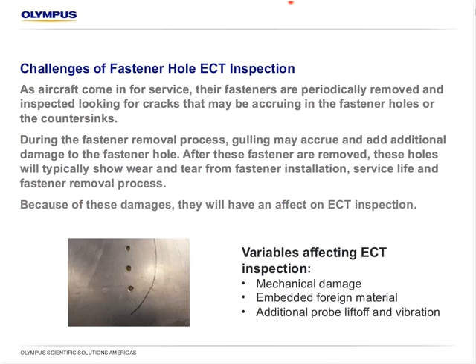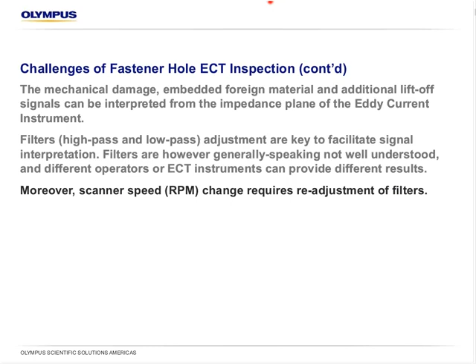The filters, typically there's a high-pass and low-pass filter on the instrument. They are key to facilitate the signal interpretation. And generally speaking, those filters are not that well understood, and different operators, or operators using different equipment, can have different results on the same part or on the same calibration specimen. So tuning the filters is always a bit tricky. Moreover, when changing the rotation speed of the scanner, one would need to readjust the filters to make sure that the band of frequencies allowed remains acceptable or allows the test to be made.